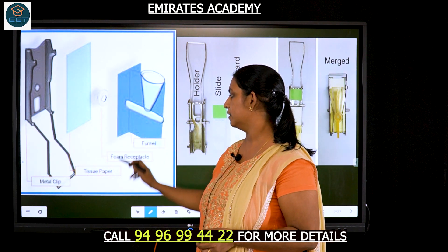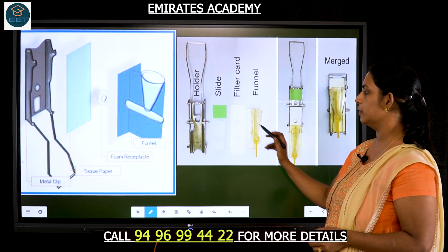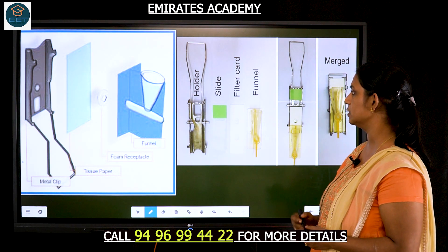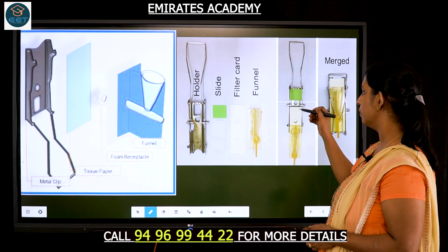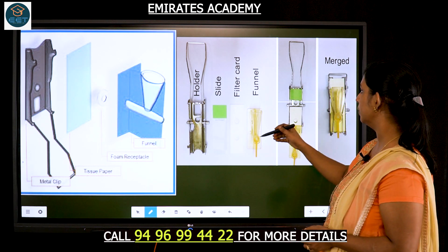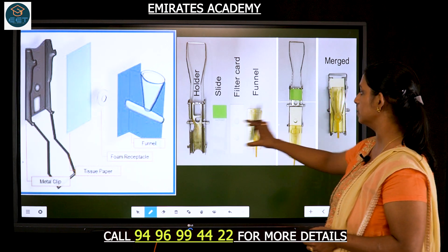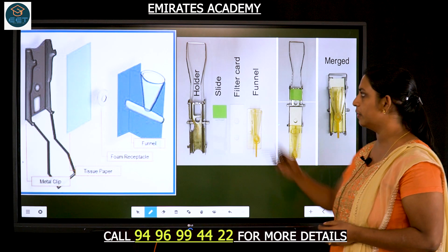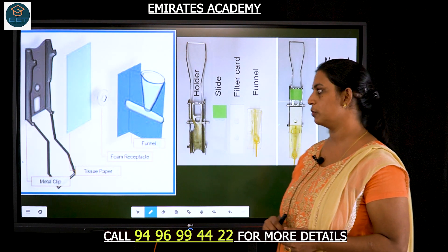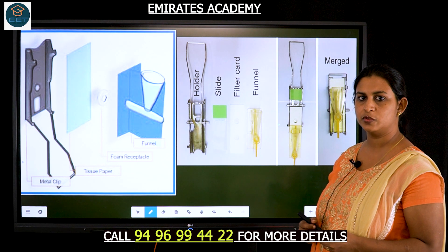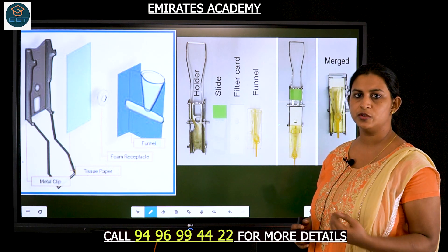This is a part of the cytospin slide. We have a funnel, then a foam receptacle, then a tissue paper and a metal clip. We have a holder, a slide, a filter card, and a funnel. The filter card is kept within the holder and the funnel is placed here. Upon joining the filter, slide, and funnel, we close the metal holder, and this total unit is placed inside the cytospin centrifuge to separate out the cells onto a slide.